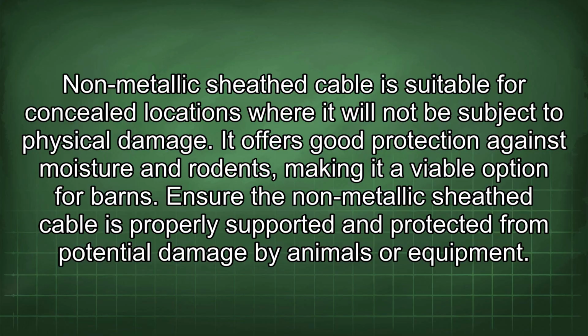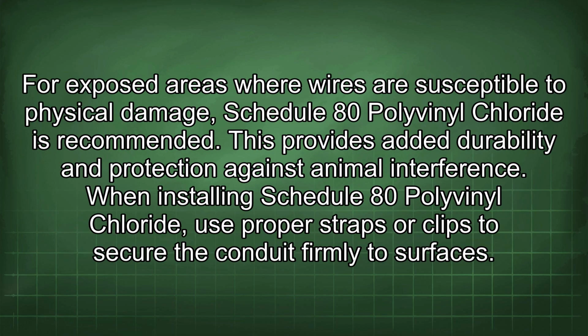It offers good protection against moisture and rodents, making it a viable option for barns. Ensure the non-metallic sheath cable is properly supported and protected from potential damage by animals or equipment. For exposed areas where wires are susceptible to physical damage, Schedule 80 polyvinyl chloride is recommended. This provides added durability and protection against animal interference.